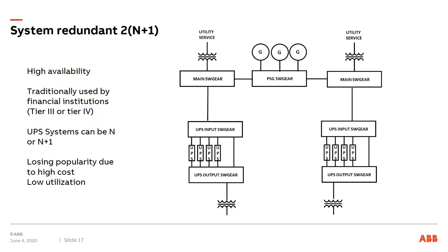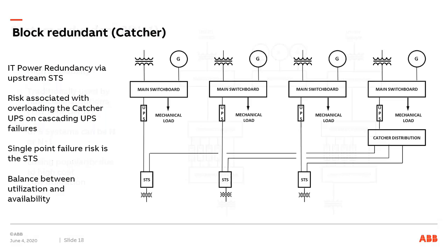So as I mentioned, efficiency is still very important, but they are very focused on coming up with designs now where they can actually increase the utilization, still have a highly reliable system, but not with a lot of idling equipment sitting around, as we see in the system redundant, like a 2N+1 system. So today we typically see two main schools of thought or designs out there. One is what's referred to as a block redundant, or a catcher system, which comes in all different ways, shapes and forms.